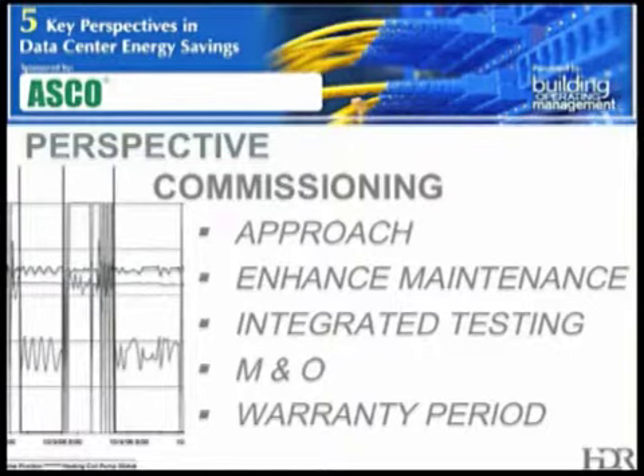We've got to align the test scripts for the functional and integrated testing with changes that have been made during the submittal phase. So that's another thing we're looking to, is to make sure that we're staying current with changes that have been made. And finally, we really need to zero in on the set points of these systems after we've had the opportunity to look at trends and fully analyze them at the end of the job.